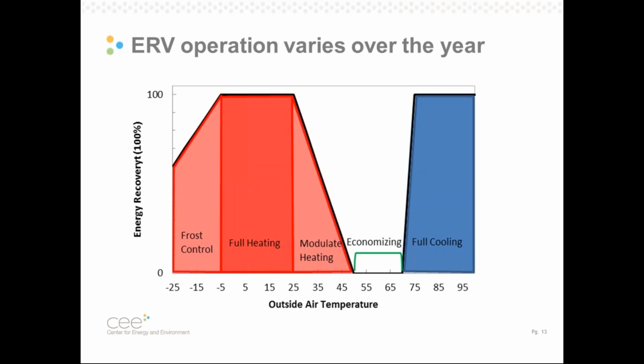In this case, we should actually shut off energy recovery units. They interfere with our ability to use the outside air for free cooling. If they were running, they'd heat up that air and reduce our ability to economize. So in mild cooling weather, we shut ERVs off to get maximum energy savings.